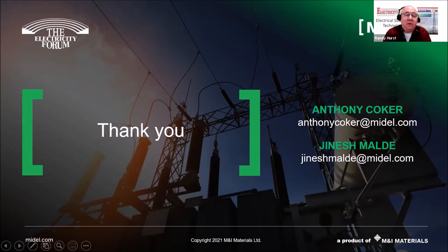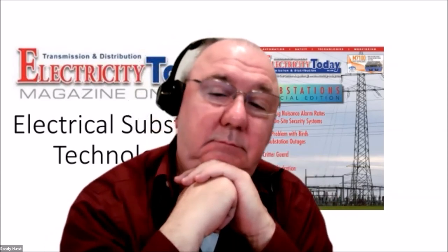One of them is from Steve Larson. Steve happens to be our substation maintenance instructor who is with Snohomish Power. Steve wanted to know, can the ester fluids be used in the load tap changer compartment of a power transformer? Jinesh? So, if this is for a retrofill application, it would have to be discussed with the tap changer manufacturer. Now, as far as if it's a new tap changer, there are tap changers that are designed to work with ester liquids, and we can provide more information on that.